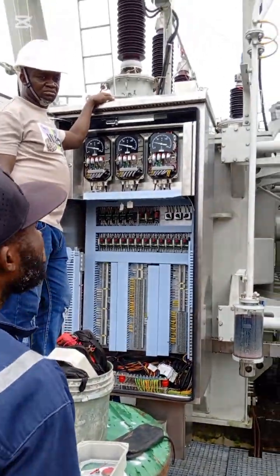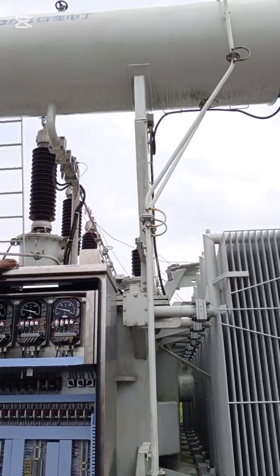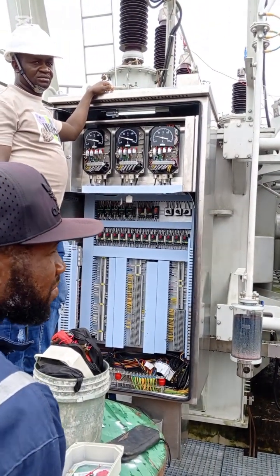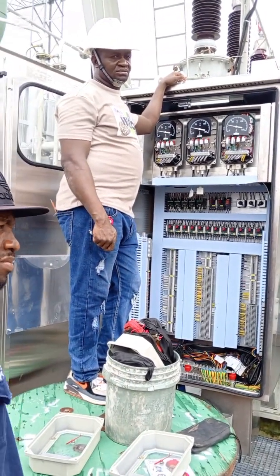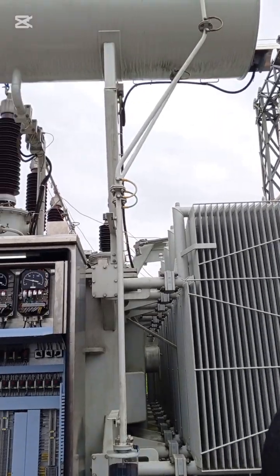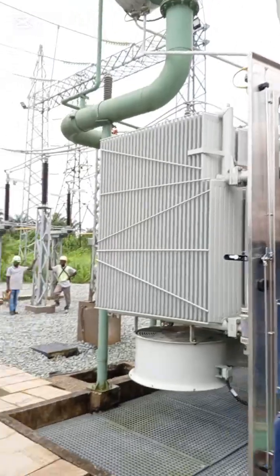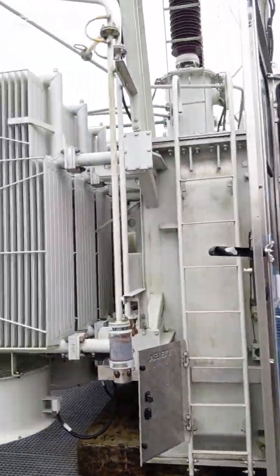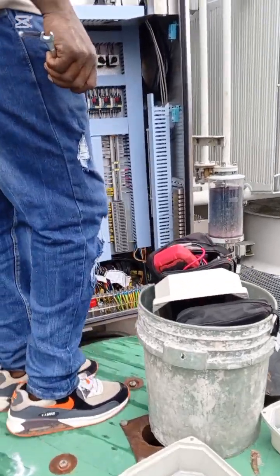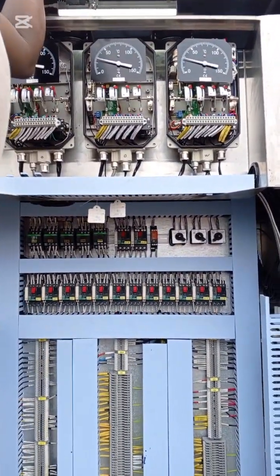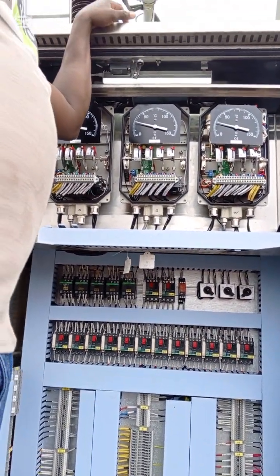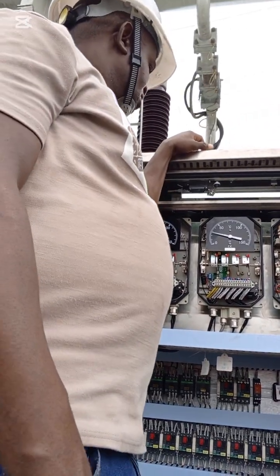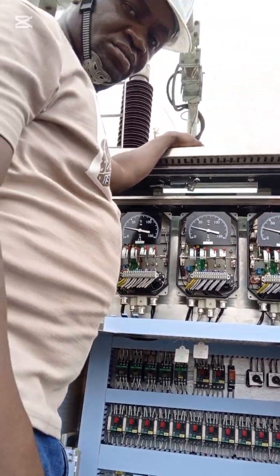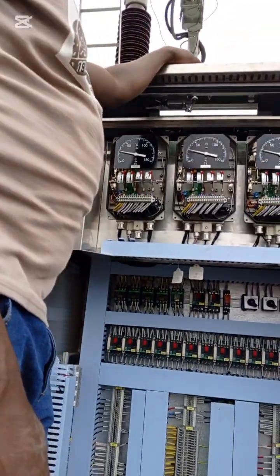Polarization index test, the ratio of the 10-minute to 1-minute IR reading, gives a deeper insight into insulation dryness and quality. 2. Winding resistance test. Purpose: measures the DC resistance of each winding on all phases and all tap positions. Why it's important: verifies the integrity of internal connections, checks for loose contacts, broken strands, or shorted turns within windings. Results are compared to factory values.